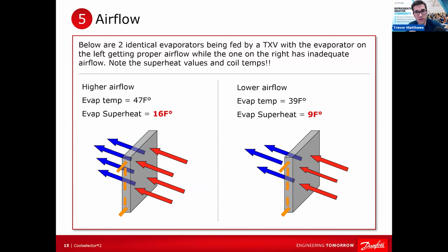Yeah, I like what you said earlier. In the last slide, you said you want to understand the system, how it runs normally. And I do this in all my trainings. It doesn't matter if it's supermarket, if it's chillers, if it's just HVAC or compressors. You got to go troubleshoot a system that's running normally. Mm-hmm. That's what you got to do. And people are like, what do you mean troubleshoot a system? You go in, you get all the systems running fine, all the pressures, all the temperatures, all the voltage on every point, every electrical point.